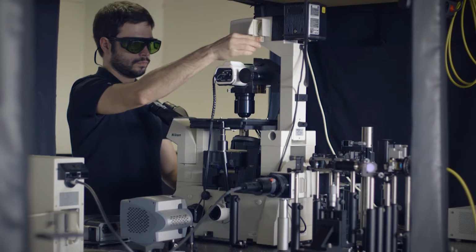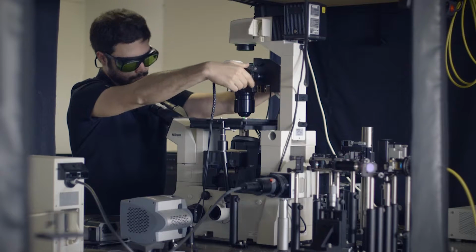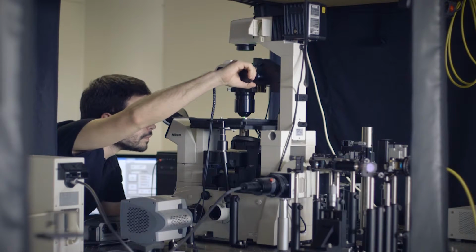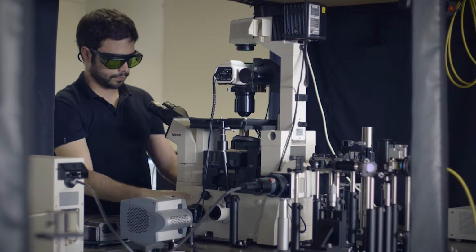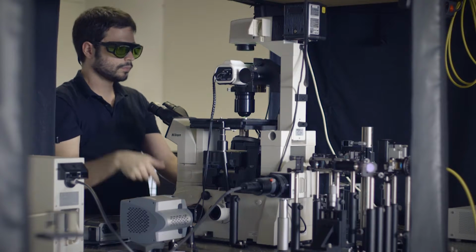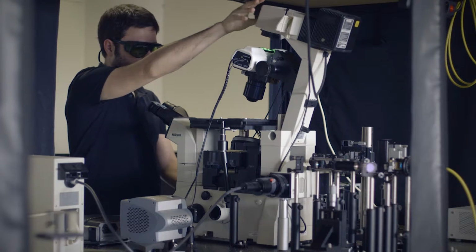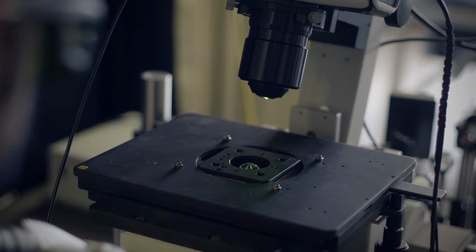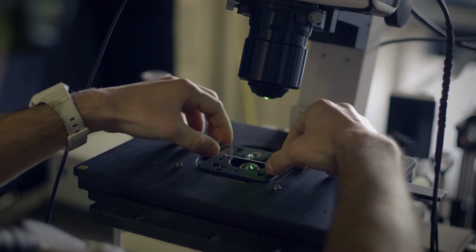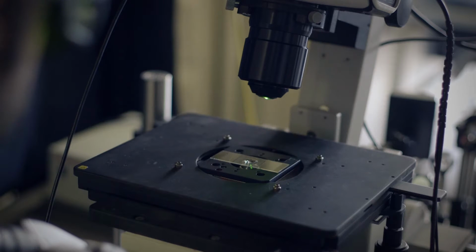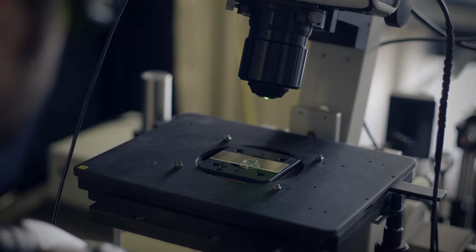Optical tweezers or optical traps were conceived in the late 80s and are now used as a complementary technique to light microscopy for the non-contact, precise manipulation of the microscopic samples under observation. It is essentially a powerful laser beam which is highly focused by the microscope objective lens. The laser is able to exert forces on microscopic particles to accelerate and trap them close to the laser focus, which is called the optical trap. For the manipulation of biological samples, a near-infrared, non-visible laser is commonly used to minimize optical damage.